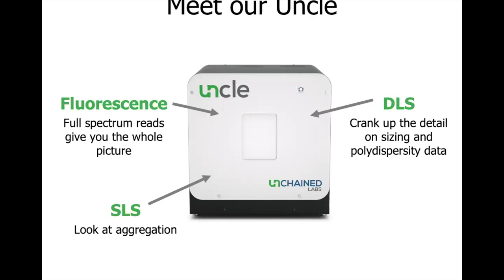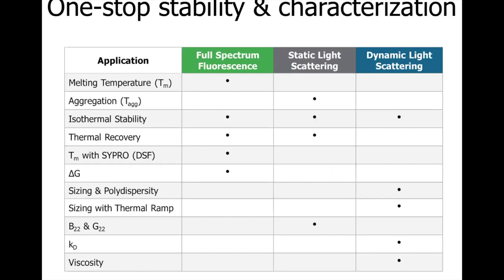The static light scattering is measured simultaneously with fluorescence and helps you understand the sample aggregation behavior. Dynamic light scattering gives you information about the sizing and polydispersity of the sample and can be used for a quality check. The UNCLE has a Peltier temperature control element and you can run experiments at a user-defined constant temperature or perform temperature ramps between 15°C and 95°C. The combination of three detection methods allows for 12 different applications that answer specific questions around protein stability.